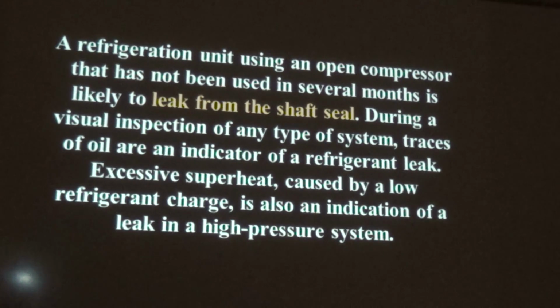We have to create a barrier so the refrigerant doesn't escape through that shaft seal. So we use a carbon ring that is constantly pressed with a spring up against the faceplate of the end bell. Over time, when that compressor is not running, refrigerant will work its way behind that carbon ring and leak out. Those shaft seals, those carbon rings, will also wear out if they're run excessively, and that's a source of a leak. If you have an open compressor with a shaft seal leak, then you can most likely consider that you're going to have to do a seal job in order to get this thing closed.